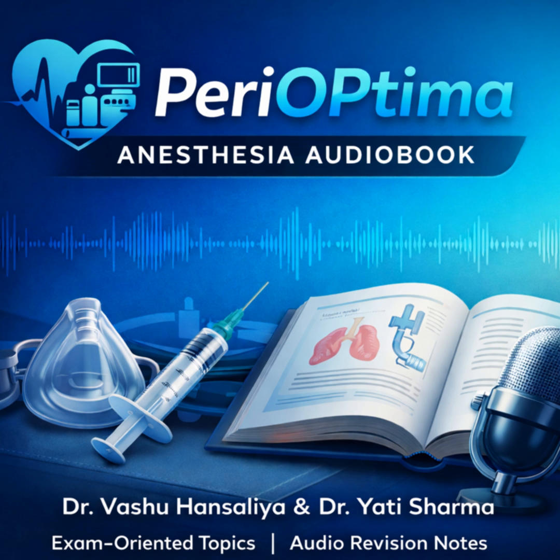Exactly. The interval must correspond to the time to peak effect, the T-peak of the drug. If morphine takes about 7 minutes to reach its peak effect in the brain, but you set the lockout to 3 minutes, what happens? Your patient will press the button, feel nothing yet, and press it again. Right. And by the time that first dose actually hits, they've already stacked 2 more doses on top of it. That is how overdose happens. Dose stacking. That makes perfect sense. So the lockout prevents the patient from getting ahead of the drug's onset.